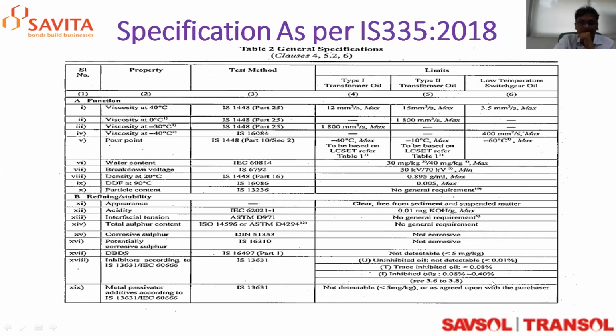One has to say this, and the rest of the tests are mentioned here. The water content should be less than 30 ppm, but normally people use something around 6 to 7 ppm during filling. We keep 5 to 7 ppm, so at the site one should get less than the required specification.